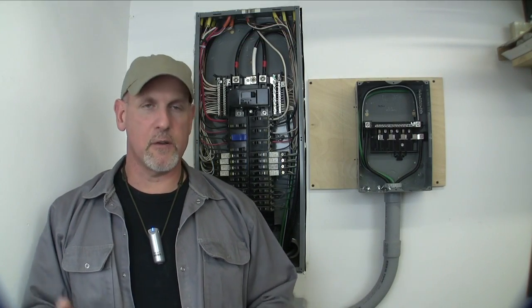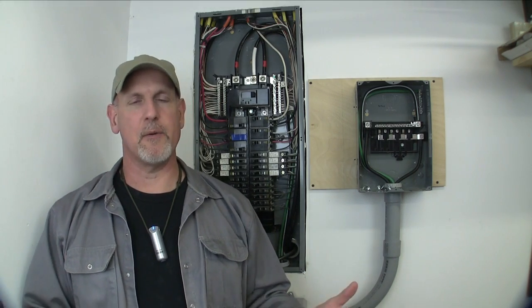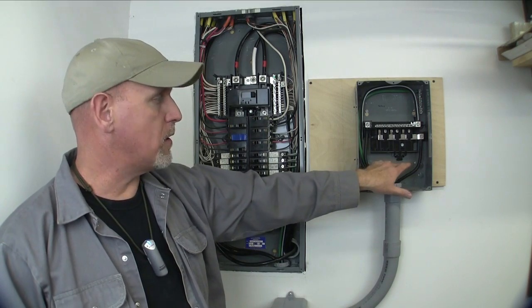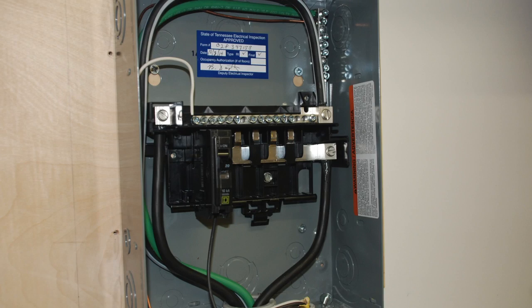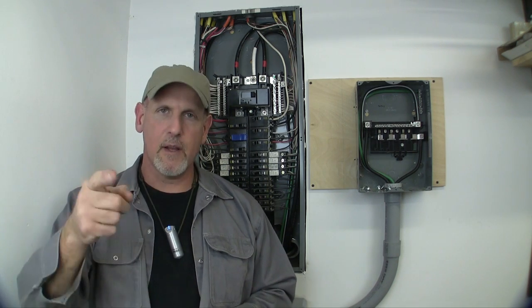One thing I wanted to point out that I failed to mention earlier is when I got in here and actually started hooking everything up, I turned off my main breaker, so I wasn't in that panel working with it hot. Some people do that, and I've probably done it before too, but today I just killed all the power so there wasn't any juice on that main panel. So for now I'm going to go ahead and get this semi buttoned back up and call the electrical inspector to come out and inspect all this and put a sticker in here showing that I've passed. At the very end of this video I'm going to show you where he's passed me on this sub-panel. Hey, I hope you enjoyed this video and maybe learned something, but like I said I'm not an electrician — so if you take a notion to do a job like this yourself, please do your own research and get your own advice. I just wanted to show you how I did mine and that it passed inspection. As always, if you like my videos give me a thumbs up, leave some comments, and subscribe to my channel. Thanks for watching.